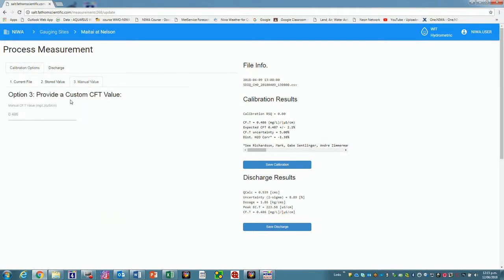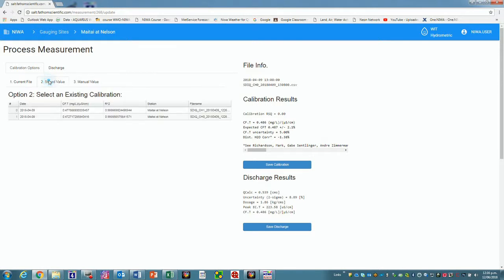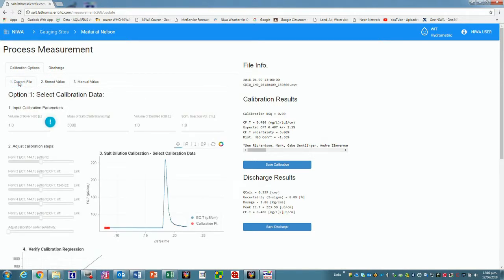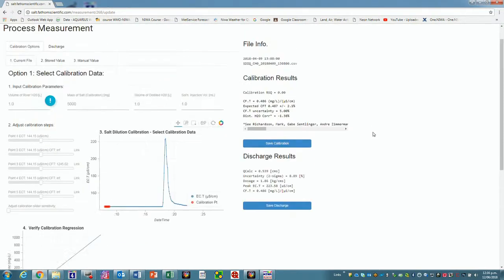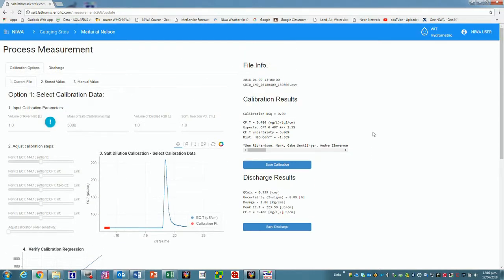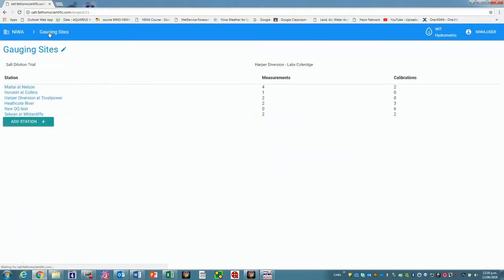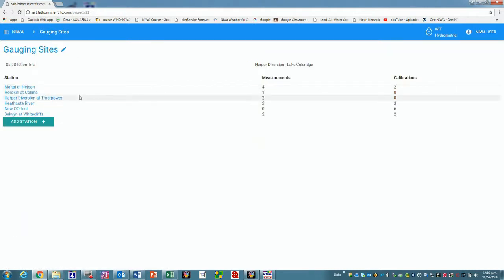If we don't have a correlation factor at the start, we didn't, haven't done a calibration, we can select one, maybe from a previous measurement that needs one to calculate the discharge. A previous measurement at that site. So something to start using online and storing our data there. Everyone can see it from this place, this website. So good to share results here and just double check that we're doing things correctly.